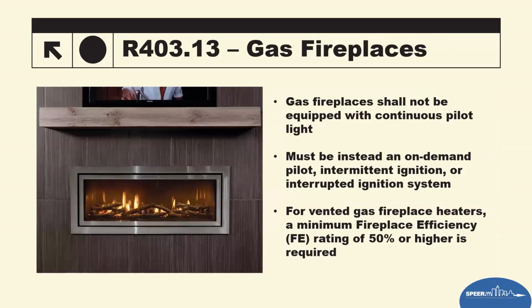Gas fireplaces. I think this was addressed in earlier codes, but they've now updated this again. Basically, we just say that gas fireplaces cannot have a continuously burning pilot light. This wastes energy when the fireplace is not in use. Instead, it must have an on-demand and intermittent ignition or otherwise similar equipment. Additionally, the fireplace needs to be vented. It also now must follow a fireplace efficiency rating. This ensures that when homeowners are not using the fireplace, it basically meets energy performance when it's on standby.